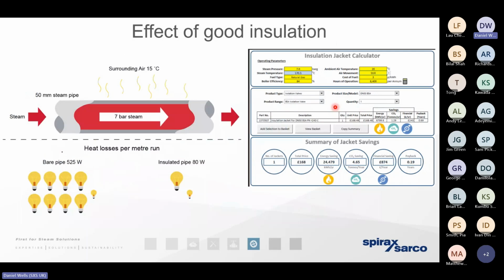So insulation, I think it stands to reason that if we're distributing very, very high temperature, high pressure steam in a carbon steel infrastructure for thousands of meters, it is inevitable. We are going to experience some heat loss. But by improving the grade of insulation that we have, we can understand the improvements we've made by reducing that heat loss. If we've reduced the heat loss, less of the steam is going to condense. We're getting more steam out the other end of the pipework.